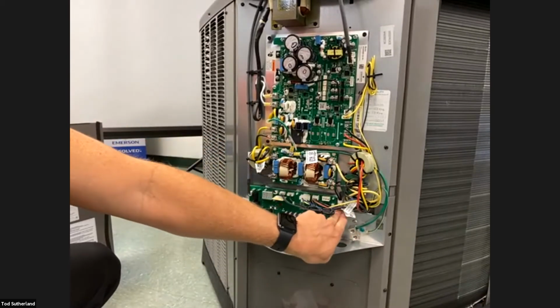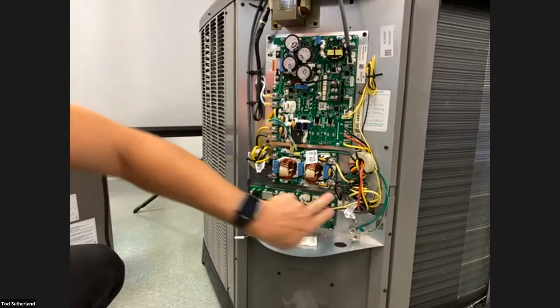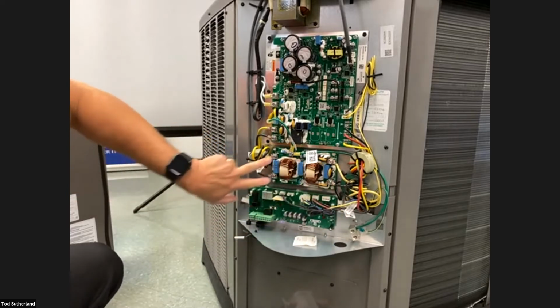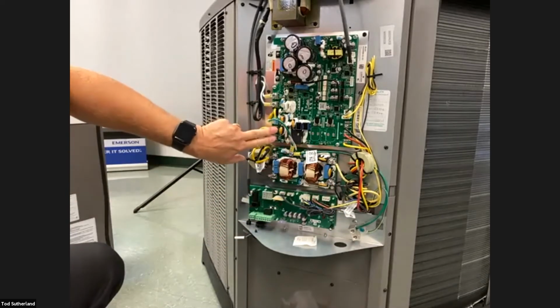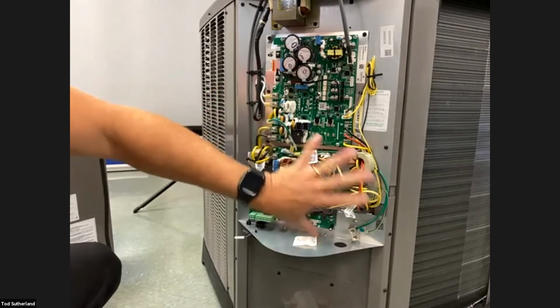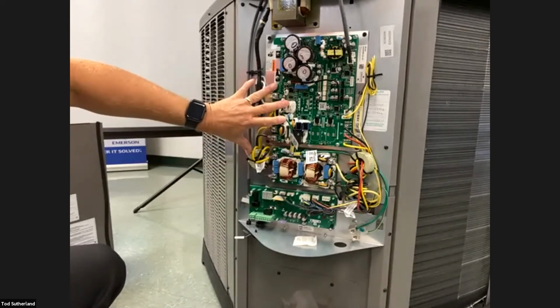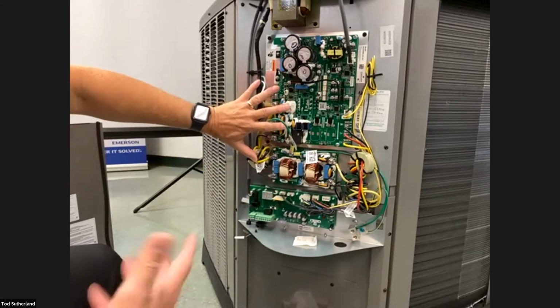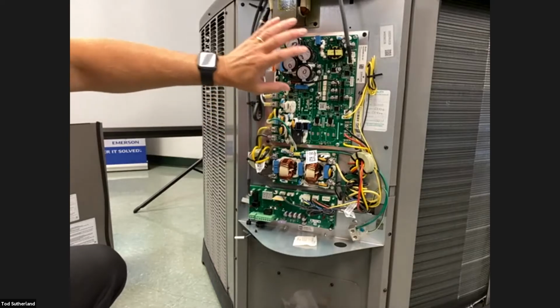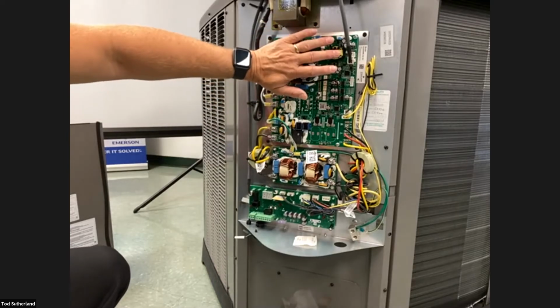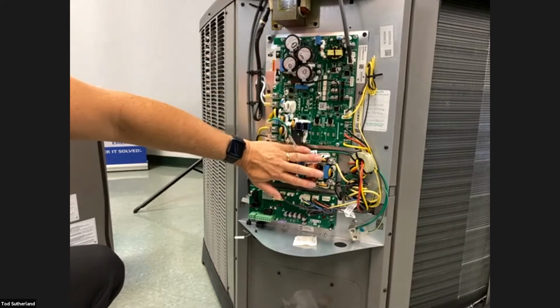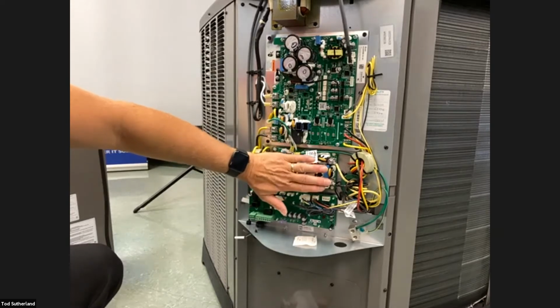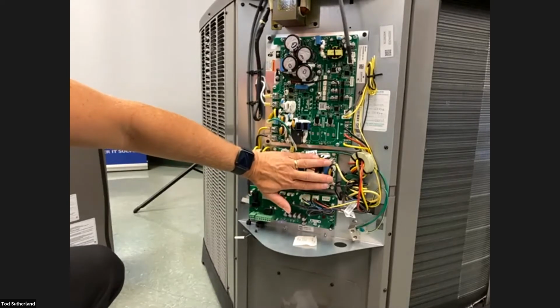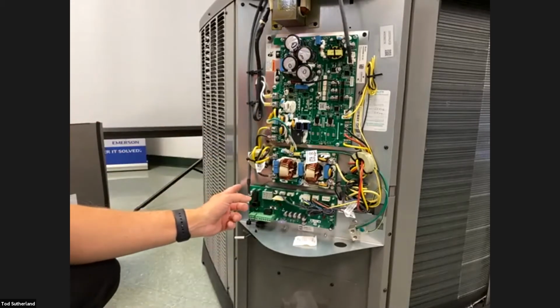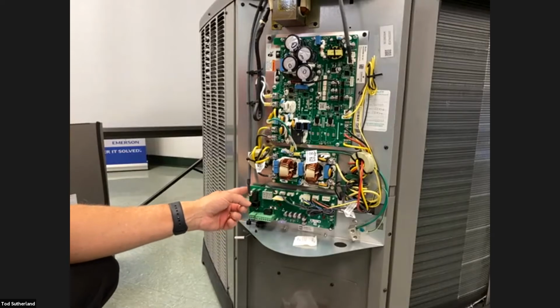So you're going to test for high voltage here, here, here, here, here, and here. If you have that all the way through, okay, and your system is not operating, then you either have a failure between this board and the compressor, or you have a failure in this filter board, which I don't think has ever happened yet. I don't know that we've ever had to replace this filter board. We've replaced this board. We're actually on the second or third version of this board.